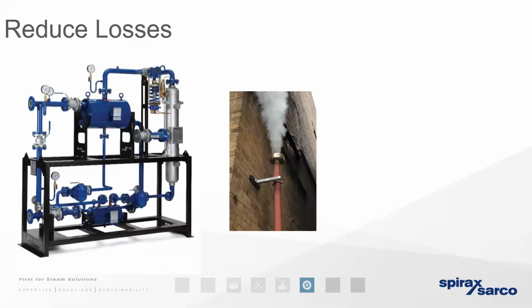This occurs whenever we've got either a failure of a steam trap or a significant pressure drop in the condensate. Sometimes a basic flash vessel can contain that energy. But whenever we're talking about a significant mass being lost, we might want to use a dedicated flash recovery skid. Huge volumes of flash steam potentially being vented away are typically indicative of a process that's condensing the steam at high pressure. The benefit here is that it will take not only the flash steam, but also the condensate on different sides of the heat exchanger.